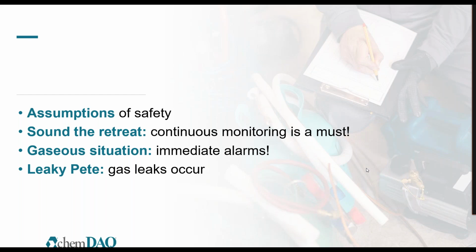Luckily, somebody walked in and they were able to get the person out, and in the short term, they were okay. And again, I don't tell this story to scare people. We don't think that this is happening every single day, everywhere you go. The issue is what happens when it does happen. Are you prepared for it? In this case, they were very lucky because somebody walked in, but if they weren't that lucky, how would you know? Now, if they had a monitor, there would have been alarms going off all over the place, and somebody would have known to run in and help that person, probably sooner than they actually found that person.